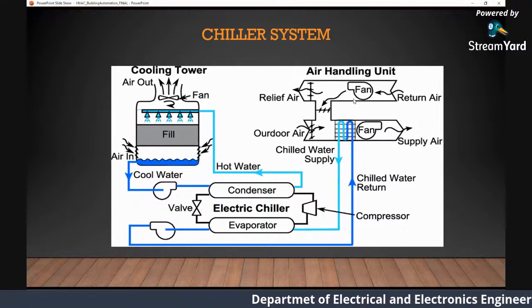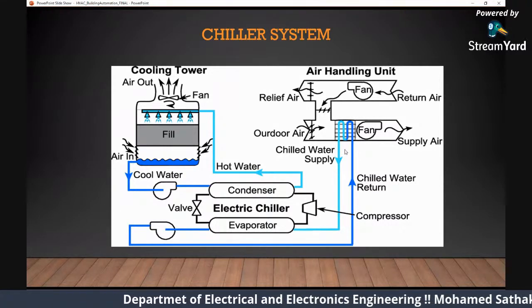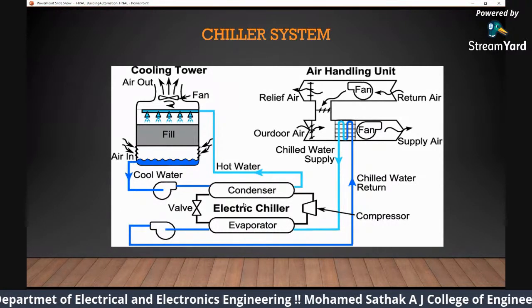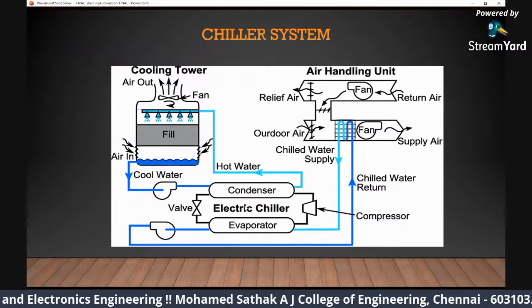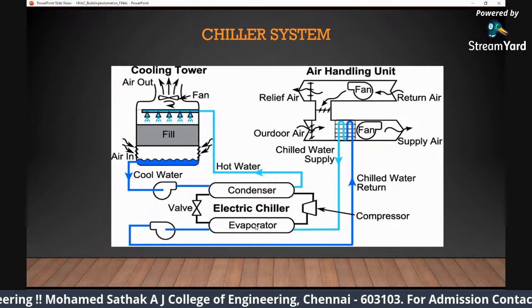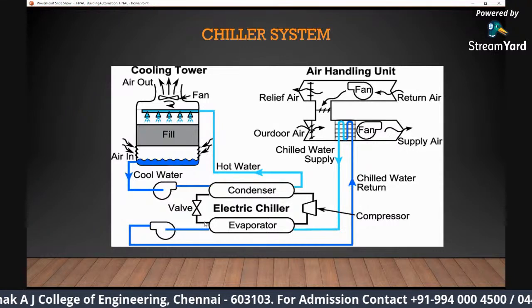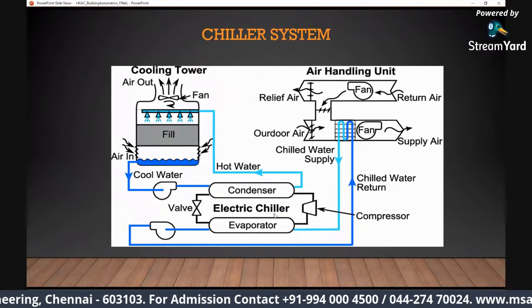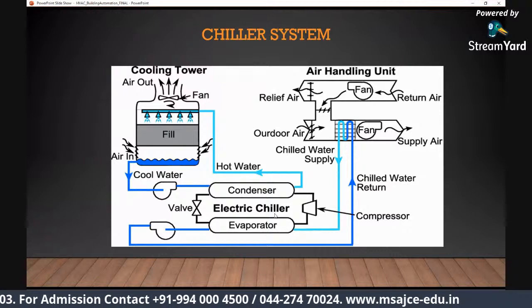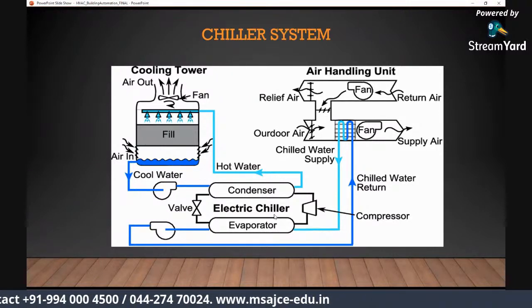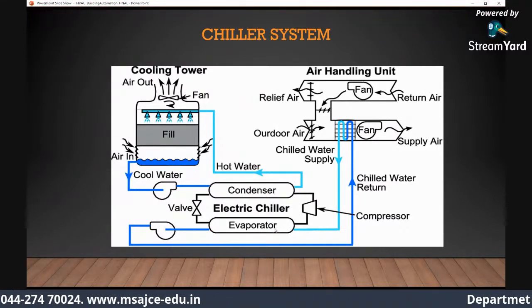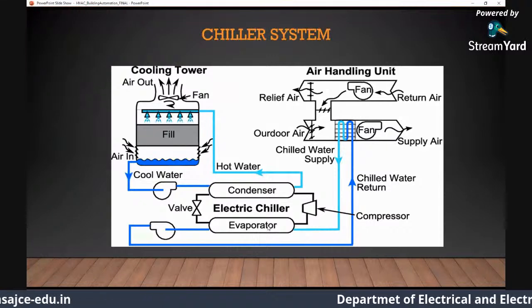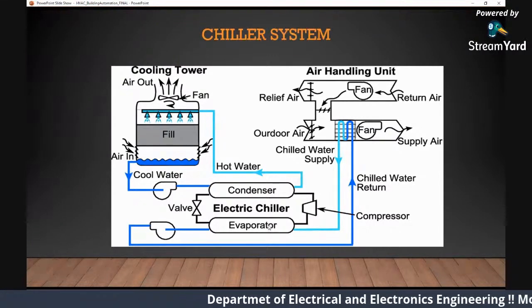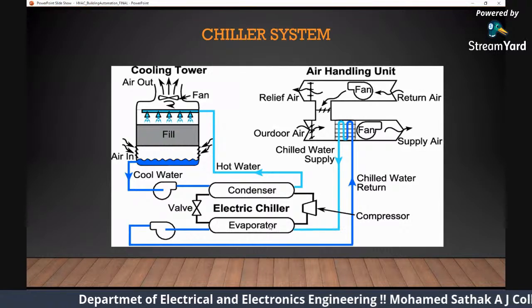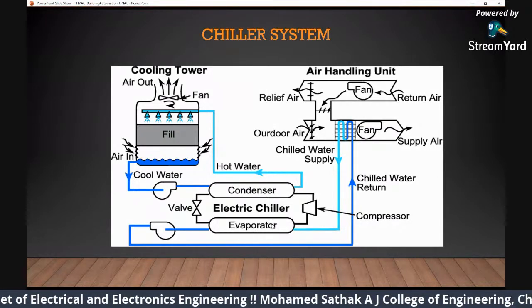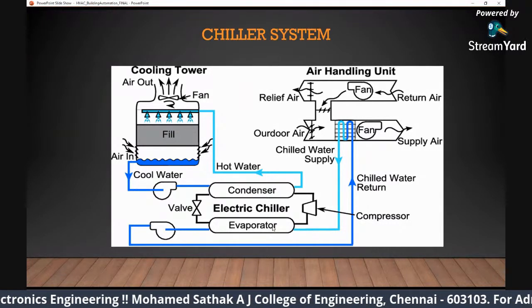If you see, there's an air handling unit on your right, which needs cold water, and that chilled water or cold water is being supplied by your electrical chiller, let's say. And as I explained, it has two sections, the condenser section and the evaporator section. What runs between the condenser section and the evaporator section is your refrigerant. There are multiple varieties of refrigerant based upon the greenhouse gases and everything. This refrigerant in the evaporator section will cool your chilled water supply based upon the thermodynamics principle, convection and radiation.